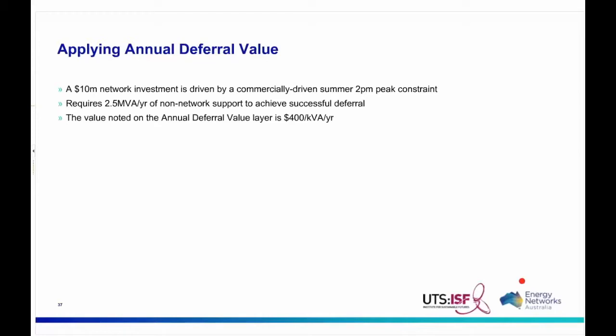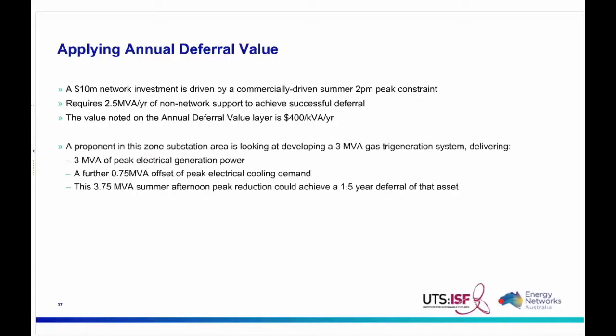Say there was a $10 million network investment driven by a commercial cooling summer peak constraint at 2 in the afternoon, requiring 2.5 MVA per year of non-network support to achieve that deferral. Say the value on the map is $400 per kVA per year, and the proponent in this zone substation area is looking at developing a 3 MVA gas trigeneration system, delivering 3 MVA of electrical generation plus 0.75 MVA of an offset to cooling demand within the building. That gives 3.75 MVA of summer afternoon peak reduction, which could plausibly achieve a 1.5-year deferral of that asset.